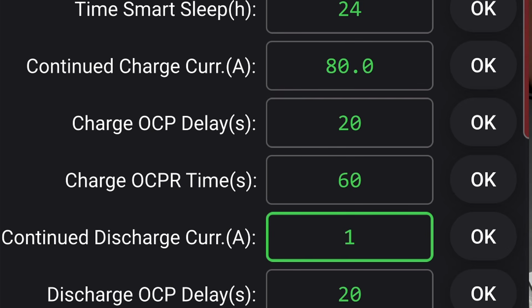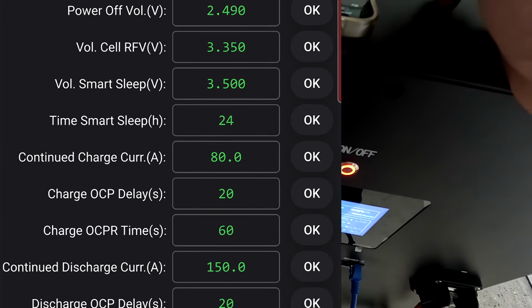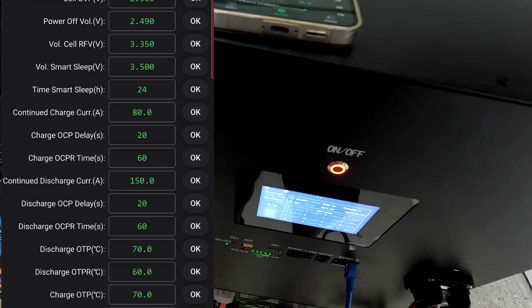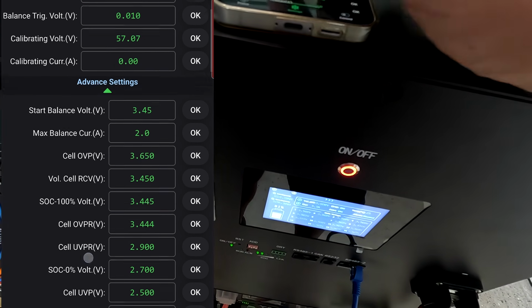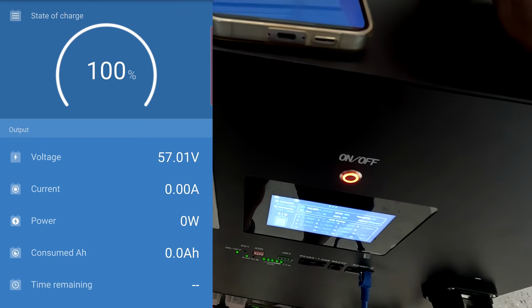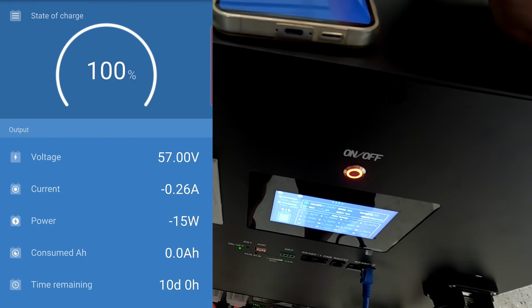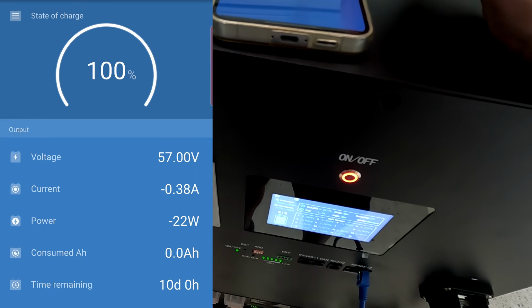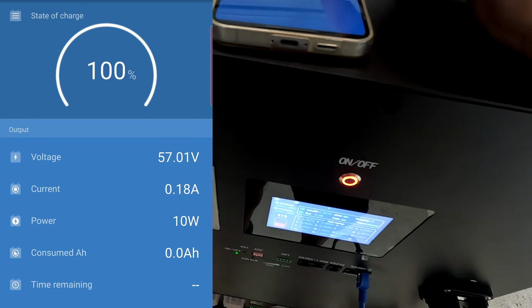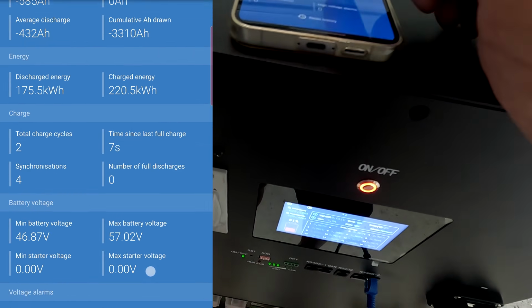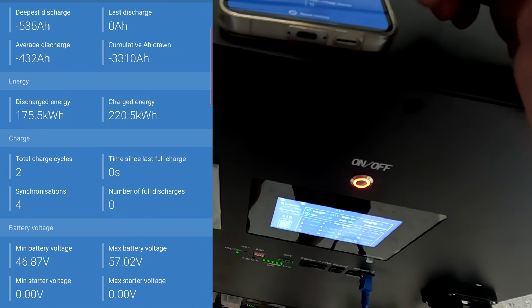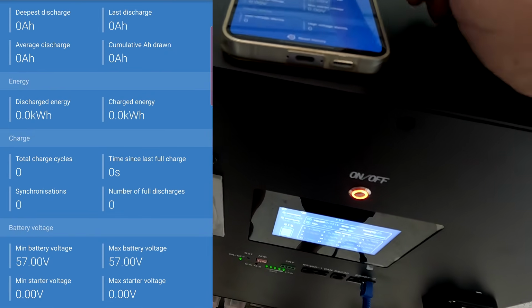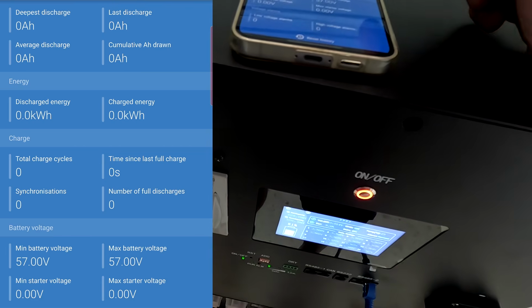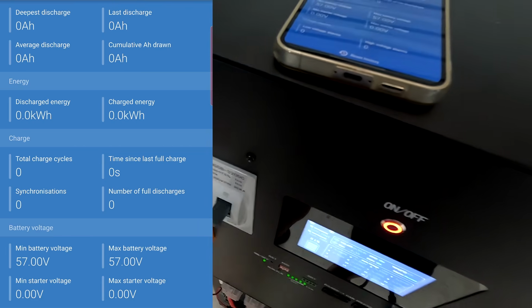Okay, we need to change the discharge current to 150 amps for this test here. Charge current is 80 amps, that's fine, we're not charging it, we're only discharging it, yeah, 150 amps maximum, just for safety purposes. And we also want to have a look at the smart shunt test. It is on 100%, shows us the voltage as well as the current, which is 0. Let's go into history and reset this all. Okay, so this is all now on 0 ampere hours, 0 kilowatt hours, nothing. And this means we can start the test.